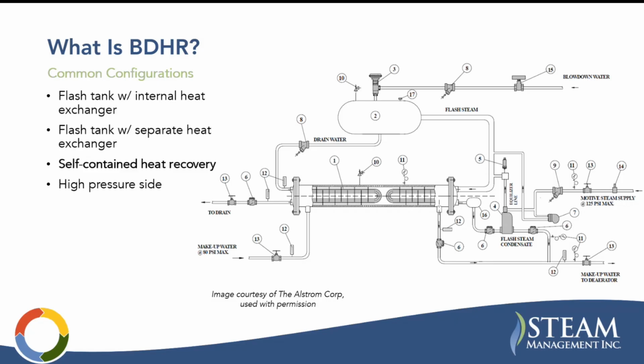What's interesting about this is, again, the steam flashes off clean. Once it condenses back down, it is clean, basically treated boiler water. And so it discharges into this makeup water line. So you're also getting that water savings from this unit. So I think it's an interesting configuration.